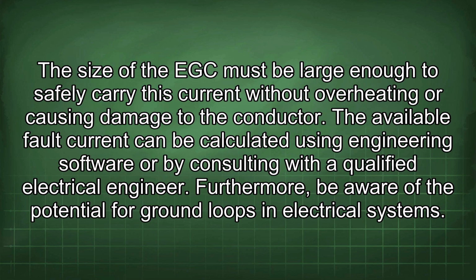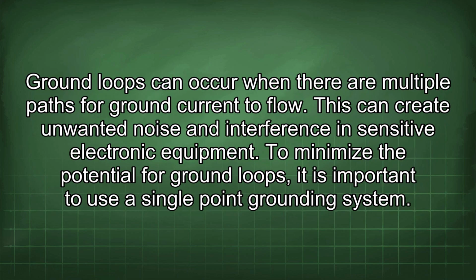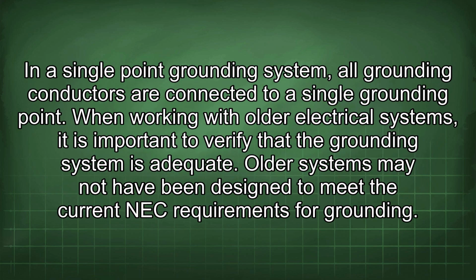Furthermore, be aware of the potential for ground loops in electrical systems. Ground loops can occur when there are multiple paths for ground current to flow. This can create unwanted noise and interference in sensitive electronic equipment. To minimize the potential for ground loops, it is important to use a single-point grounding system. In a single-point grounding system, all grounding conductors are connected to a single grounding point.